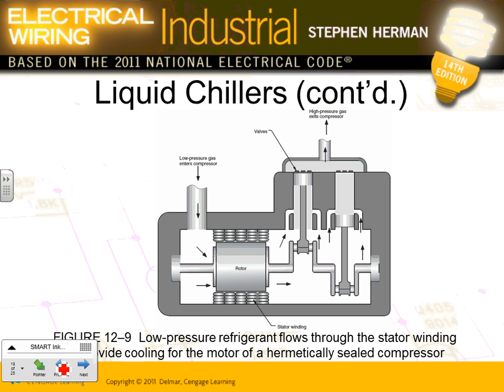Here's your motor, guys, and look how they bring the refrigerant right around the motor as it goes through the compressor. So when you bring the chilled refrigerant right around the motor of the compressor, what do you think is going to happen to the motor? It's going to cool it down. That's how they cool it, and they can abuse it a little bit more. That's how they're treated differently, other than any pump that's sitting there, because it doesn't have a chiller or refrigerant coming and cooling it. So it's specially cooled.